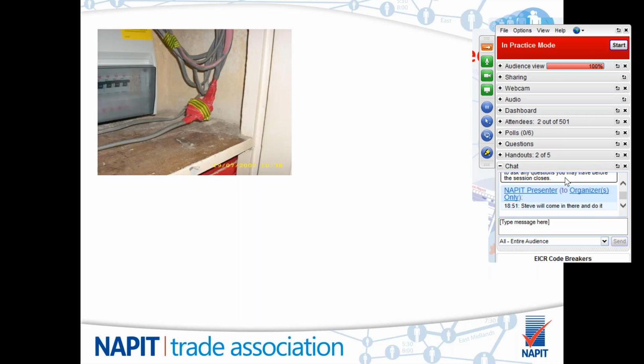I'm afraid PVC tape is not an enclosure. We all have PVC tape in our toolboxes. I know, yeah, it's still in mine, even though I'm getting long in the tooth. It is still there, and we use it for a multitude of things. But as an enclosure and protecting people from live terminations, I'm afraid it's just not thick enough. It's made of insulating material, but it's not thick enough to give us that insulating property that a cable sheath would, or an insulation. So therefore, to me, that's a C1.